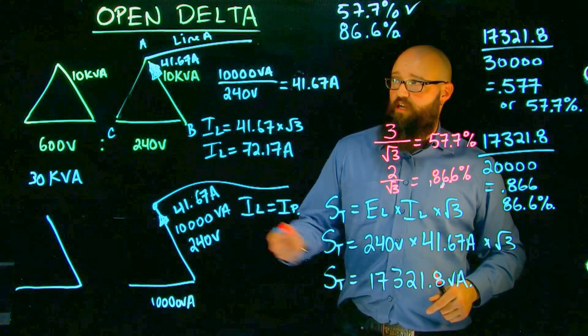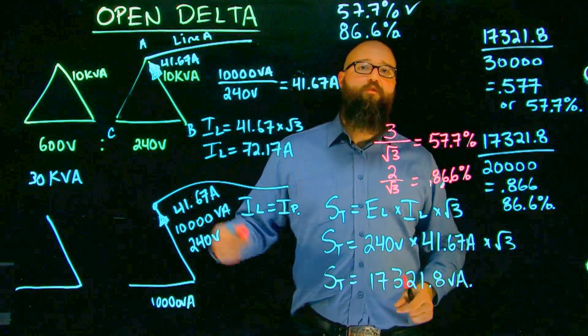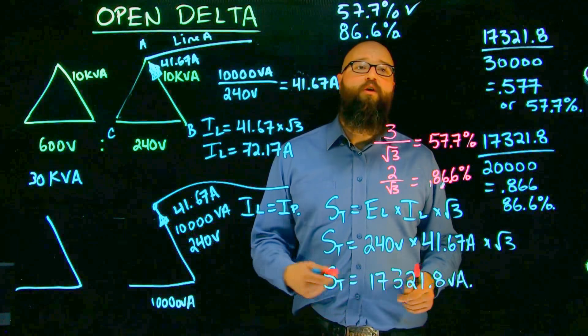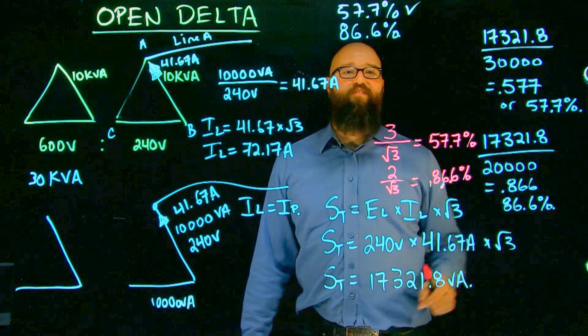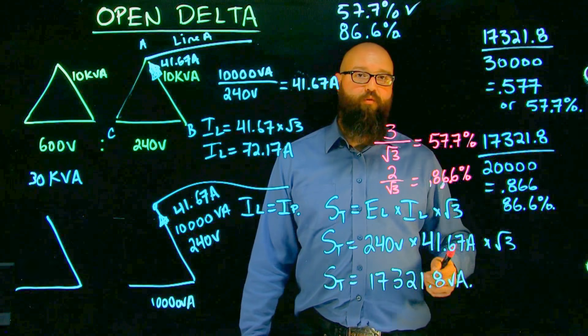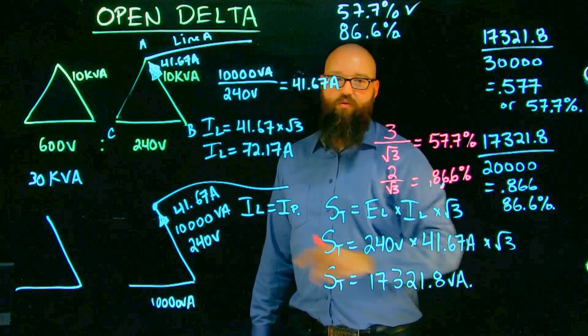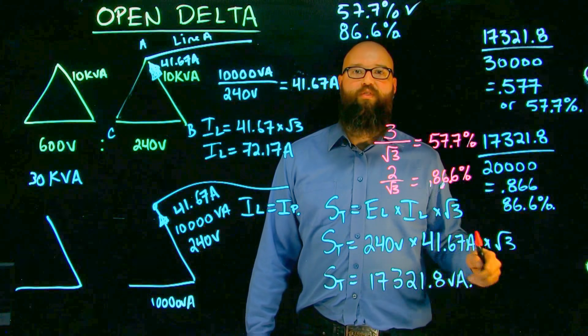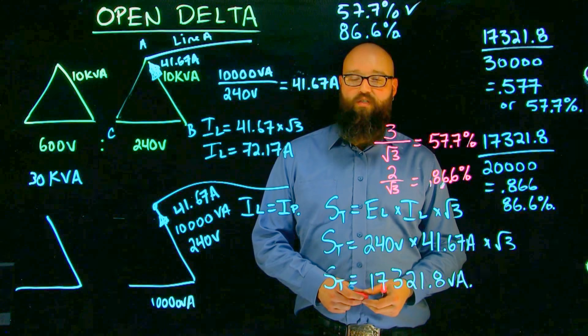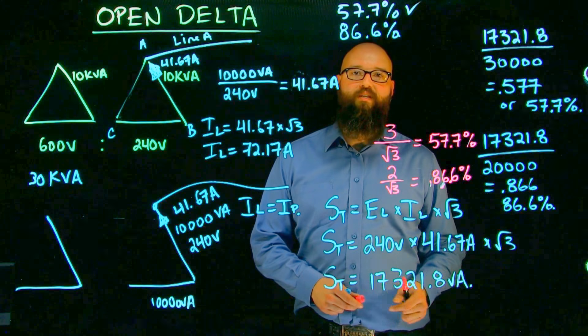Okay, hopefully this has helped. Okay, key thing to remember about open delta, when we do lose that, that third transformer, we reduce our overall capacity by 57 or to 57.7%. And we reduce our capacity of the two down to 86.6% of what they normally would be. Again, hopefully this has helped. Thank you for watching. We'll see you next time. Bye-bye.